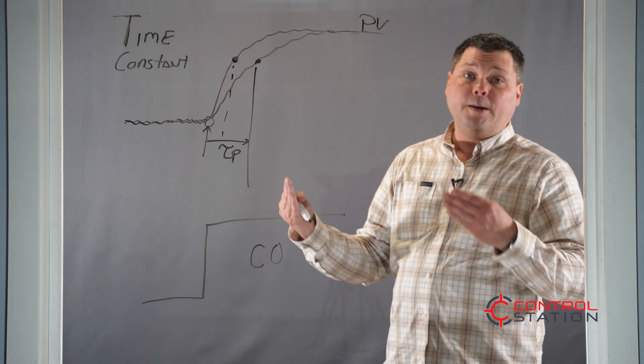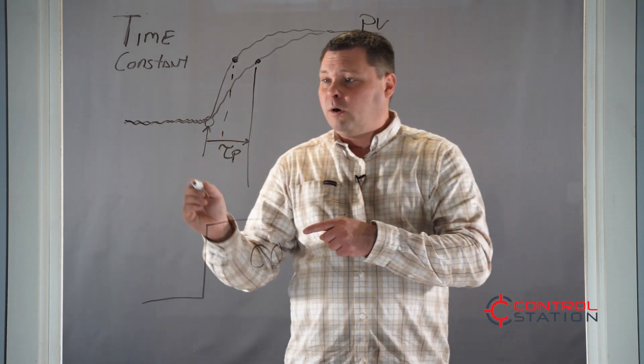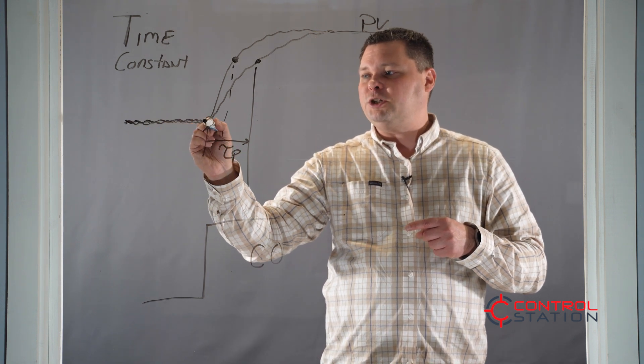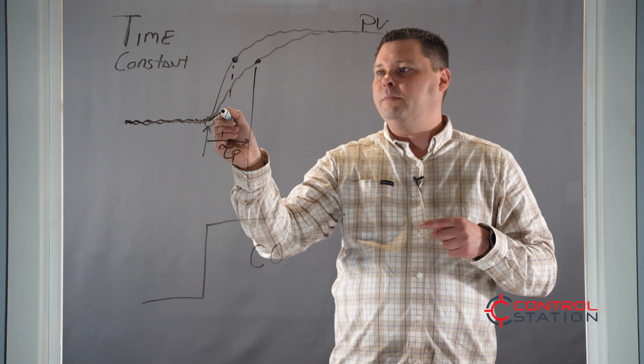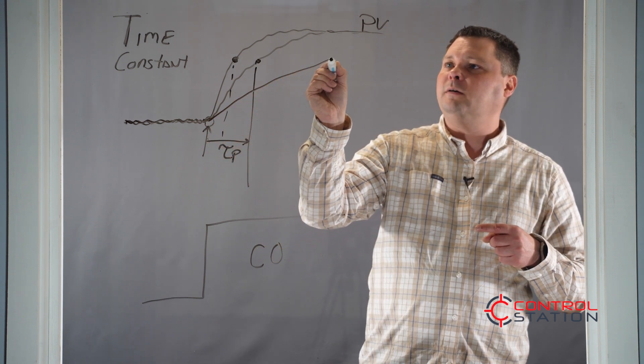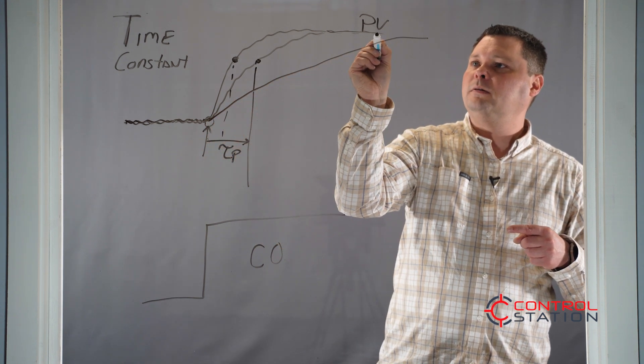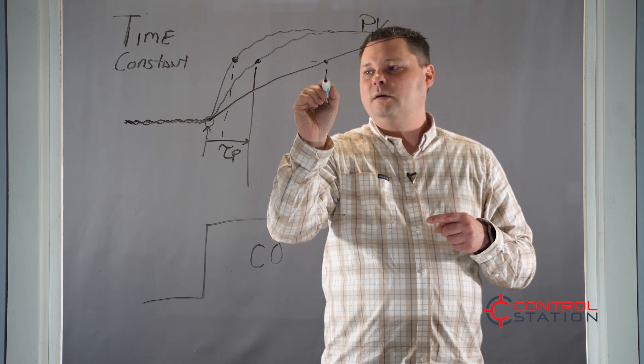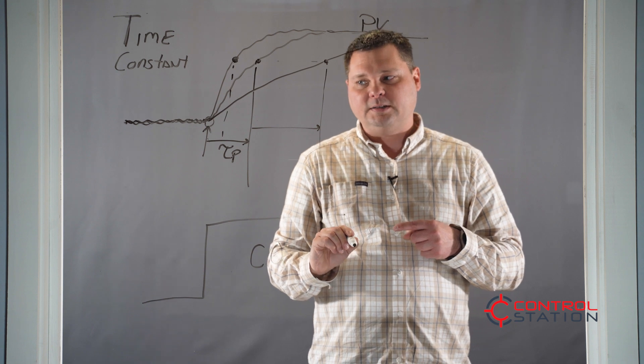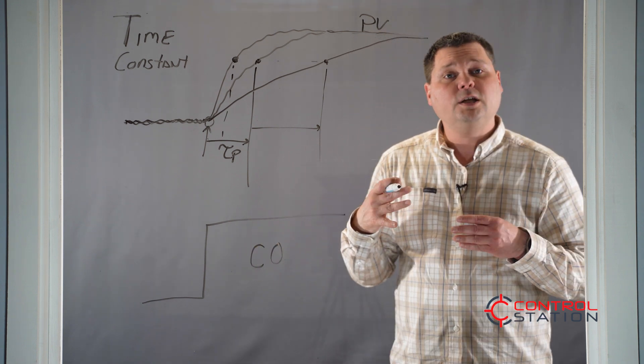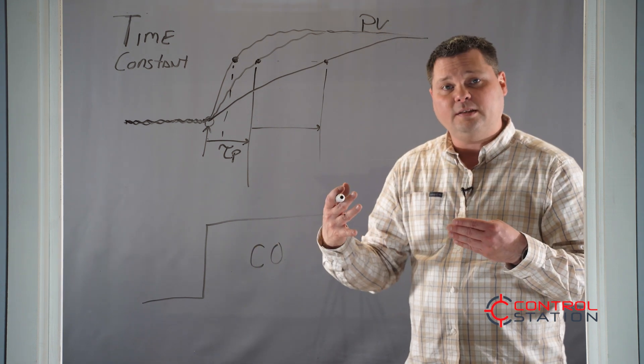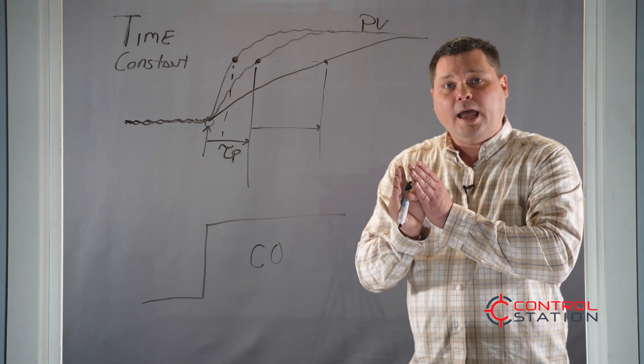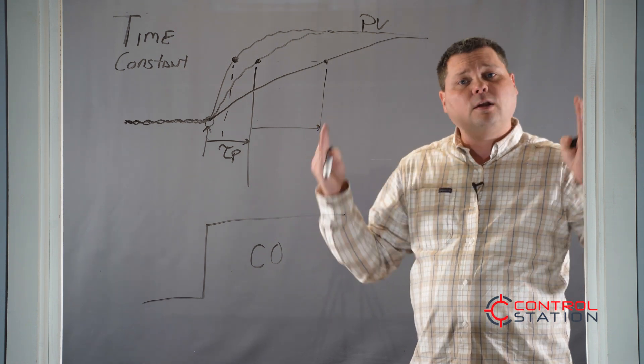You could have a very slow loop like a temperature controller, where if I had a slow process, it would still start at the same position, take off at the same time, but it may take a while to actually steady out, in which case the time it reaches 63% is there. And so you can see that's a much longer time constant. So the time constant is related to how fast does it get there? A smaller time constant is a faster process. A larger time constant is a slower process.